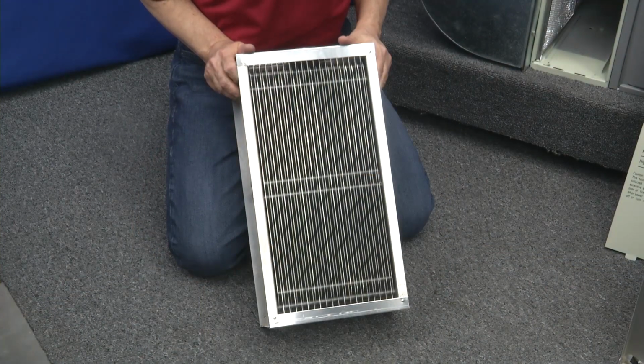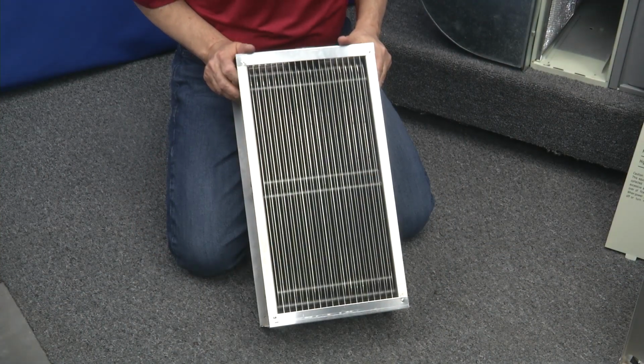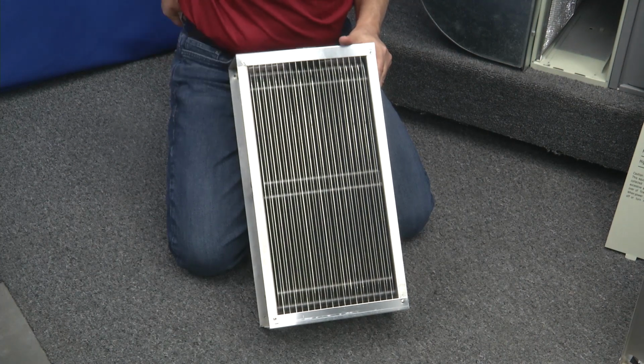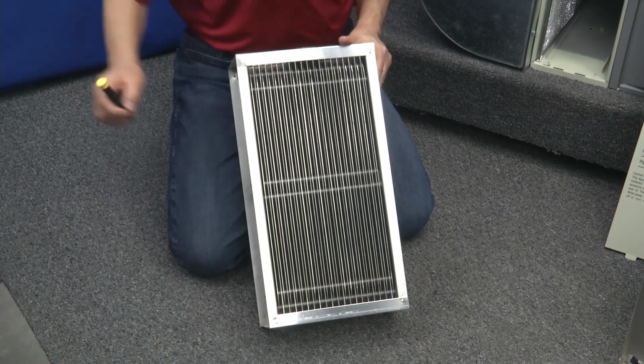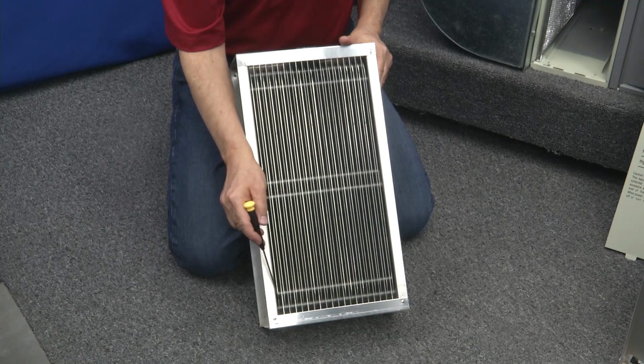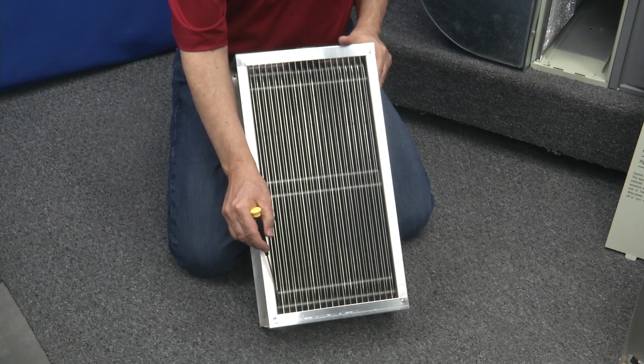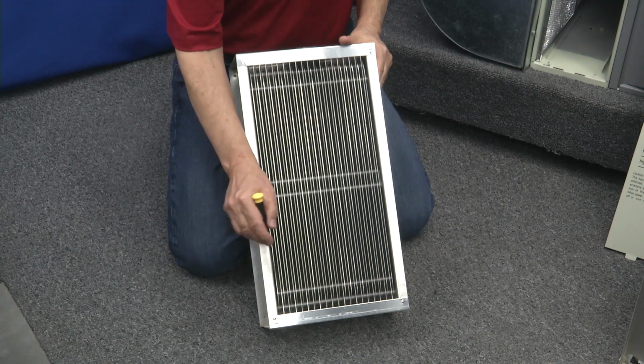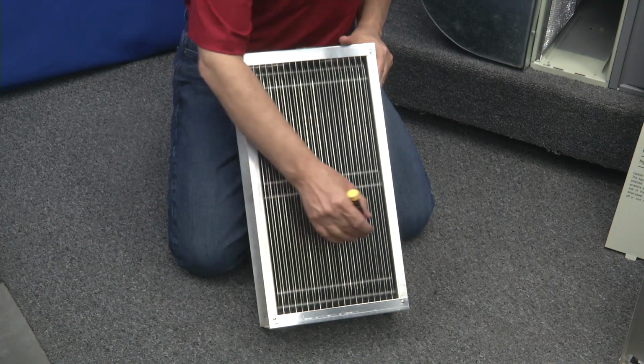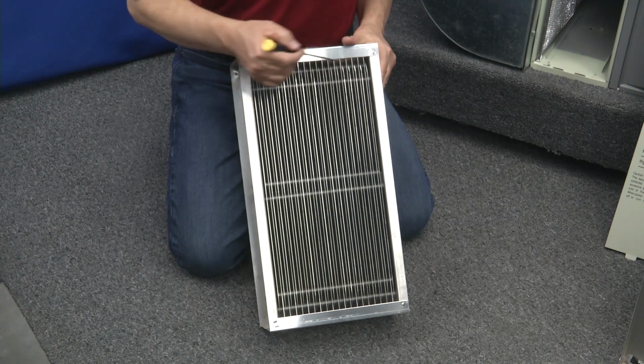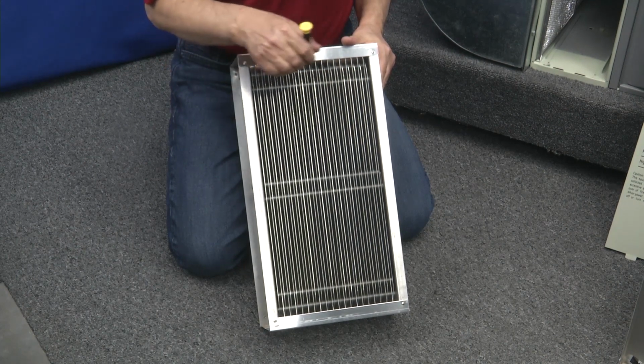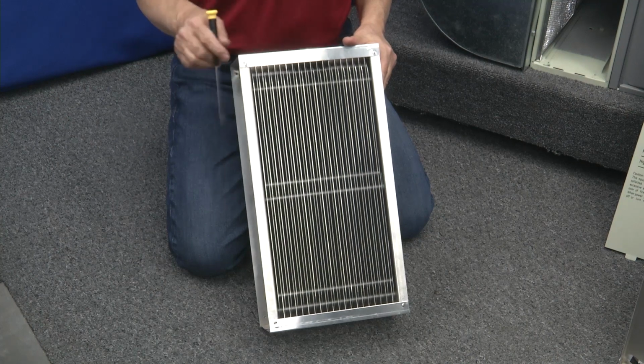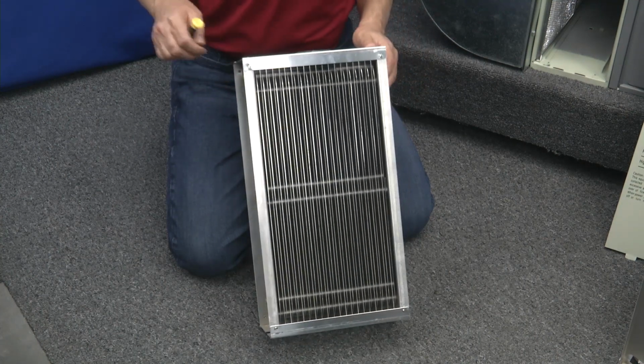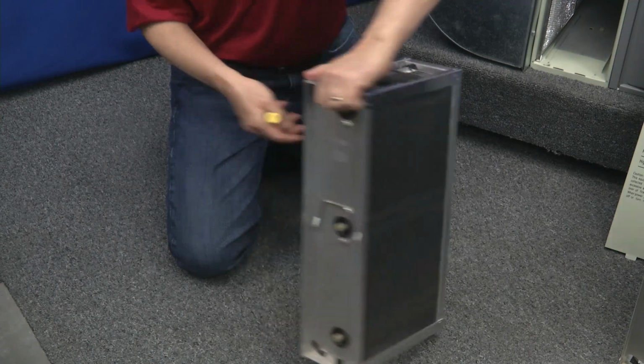This is the cell that was acting up. We're going to inspect it closely and look for things like bent fins. One common issue is that during washing, one of the little corners gets bent. The fins all need to be parallel to each other, nice and straight, no bent corners, no wavy plates, nothing loose, and no obstructions between the plates. We're going to check that side and the other side.